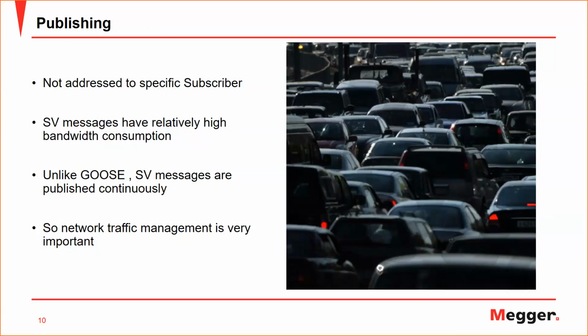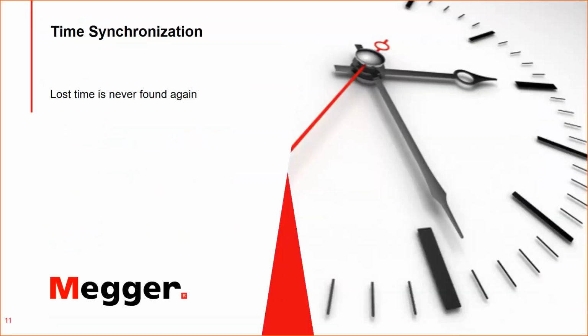If we connected as many as, for example, 80 streams to a network switch that has a link of 100 megabit per second, this will cause it to be jammed with traffic and thus losing these messages which are required to be delivered continuously all the time from this stream. So that's why it is very important to have network traffic management when you are talking about sampled values. And another topic that is also very important is time synchronization. When you don't have time synchronization between, for example, the different parts of your system, the merging units that are connecting to your IEDs, bad things could happen.